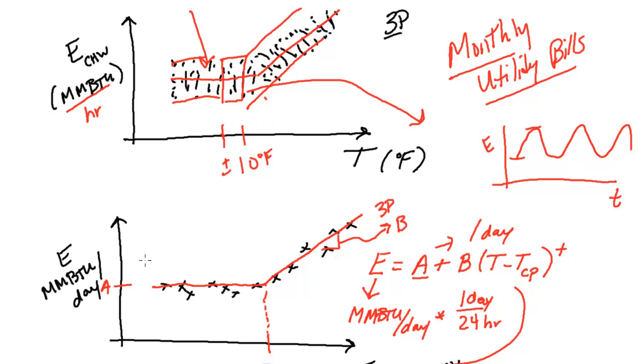So, this method always will start looking at monthly utility bills, and they're day normalized. So, again, this is an average energy use per day for a given month. And if you fit one of these linear change point models, you'll get something like this. And this is just one example. There's different model shapes, but this is one. And you're hoping that this has a pretty good fit in this method.